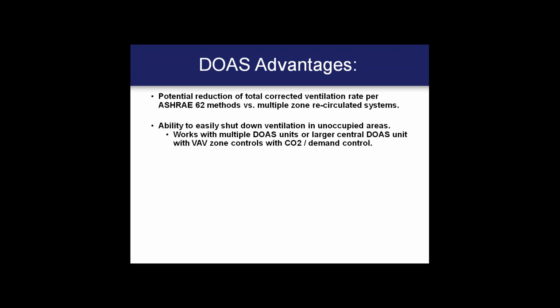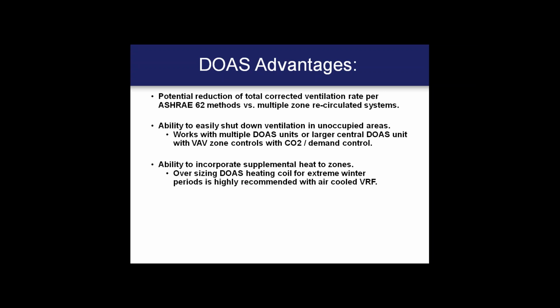Second, I think the ability to easily shut down ventilation in unoccupied areas. When you're providing DOAS units, especially decentralized DOAS units, and a lot of VRF manufacturers offer that or are beginning to offer that, in a lot of cases they're units that can connect to the VRF system or are their own variation of the VRF system themselves. That allows you to shut off certain areas of the buildings that aren't in use for large hours throughout the day. And then, of course, you can move into larger centralized DOAS systems, and for buildings with high occupancy density, take advantage of VAV controls with real precise demand control ventilation in those high occupancy areas.